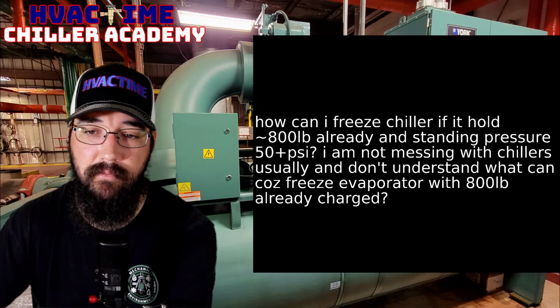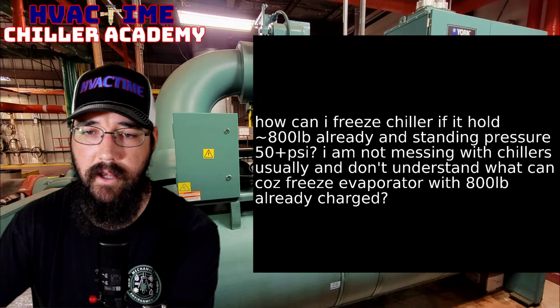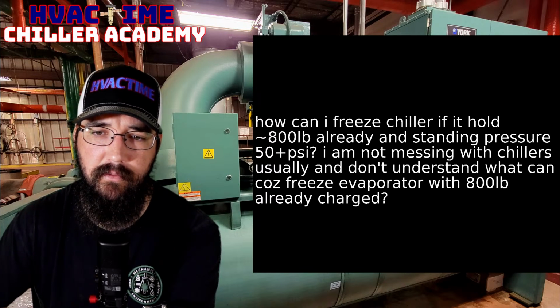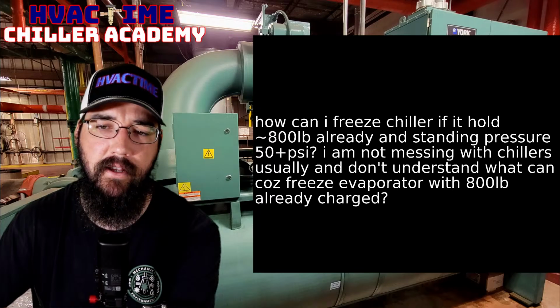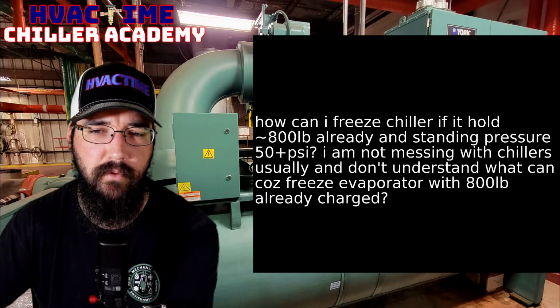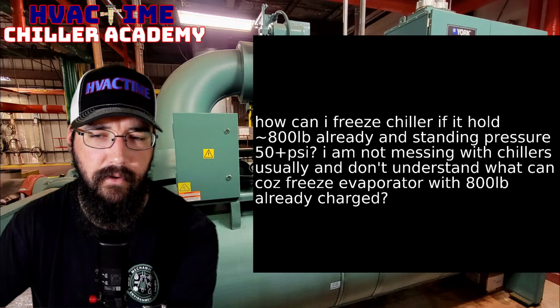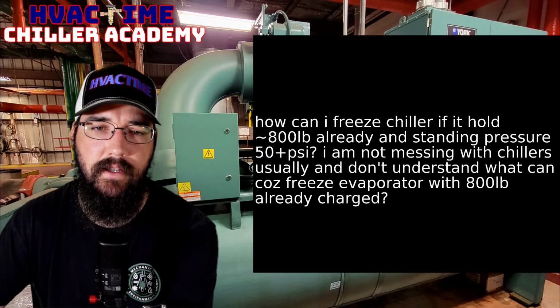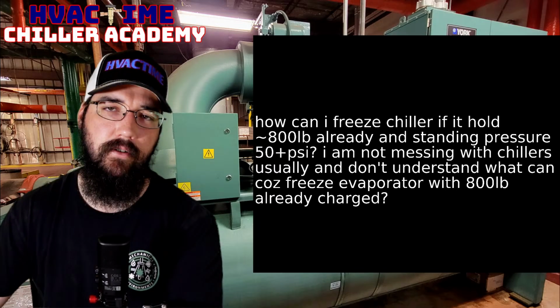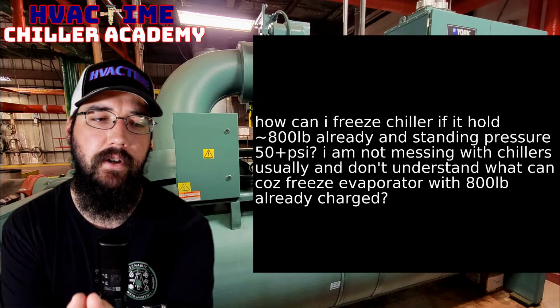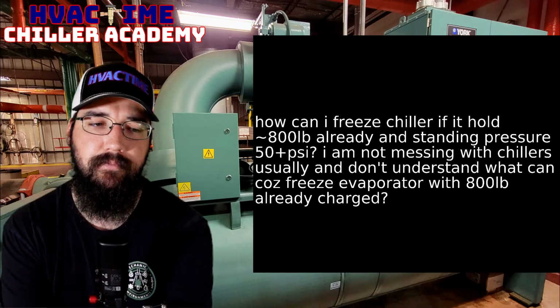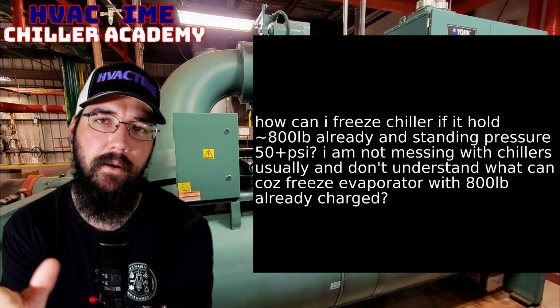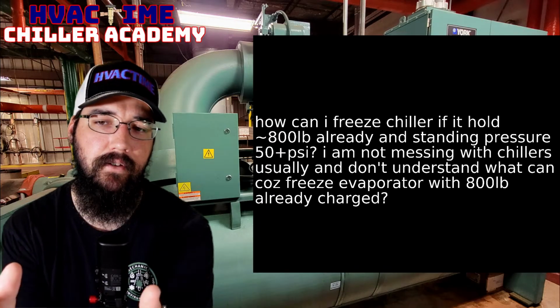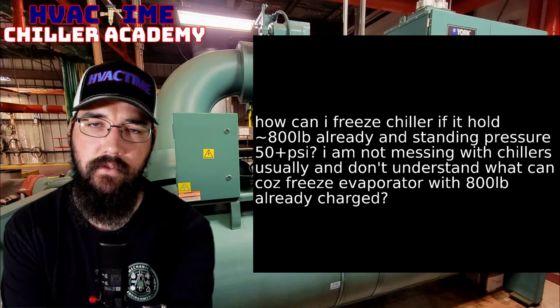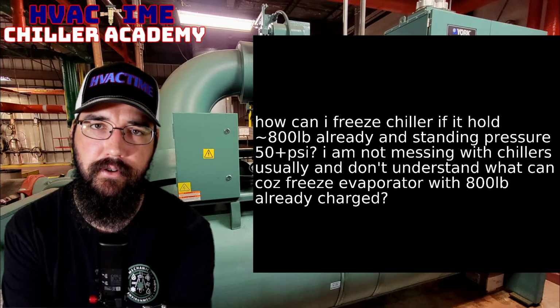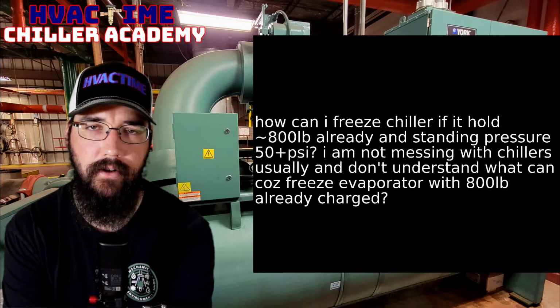We don't know the refrigerant type you're dealing with, but since you've got 800 pounds and you're over 50 psi, I'll assume it's probably R-134a maybe. Either way, the key here is your saturation temperature — we need the saturation temperature to be above freezing, period, whatever refrigerant you're using.